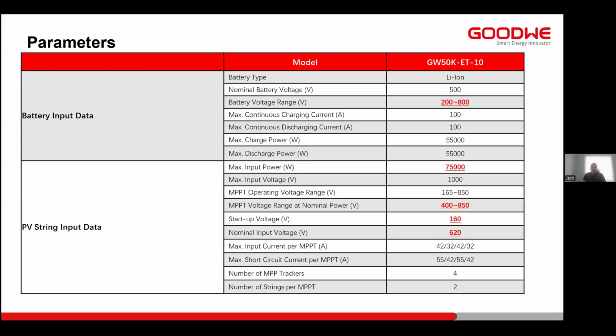Taking a look at some of the parameters, most notably on the DC input or the battery input, we support a battery range from 200 to 800 volts, with nominal voltage being 500 volts. In terms of the PV string input data, the unit can utilize a maximum of 75 kilowatt of PV power. That could either be 50 kilowatts for loads, and then 25 kilowatt going to the battery simultaneously, or vice versa, 25 kilowatt for the load and 50 used for battery charging.